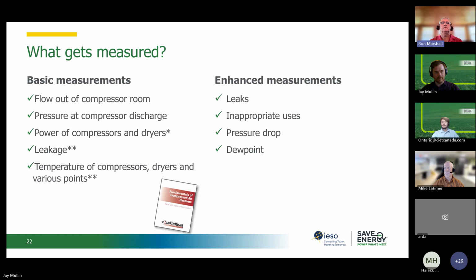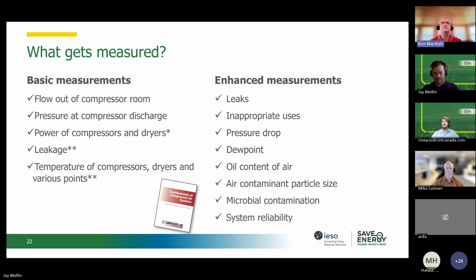Enhanced measurements could be done: leakage, special leakage work, a survey of inappropriate uses and measuring the inappropriate uses, pressure drop at various points, dew point of the air coming out of an air dryer, right? The oil content, there are measurement instruments that can measure that. If you're in a food grade food plant, it's very important to have clean compressed air, especially if it's getting close to or contacting your product. There's even specialized instrumentation that can do laser measurement of particle size. Very often that's important in, say, pharmaceutical or clean room applications, right? Food grade plants also need to reduce the microbial contamination. So you can measure that as well. And system reliability, right? Enhanced measures that could be done in addition to the basic measurements.